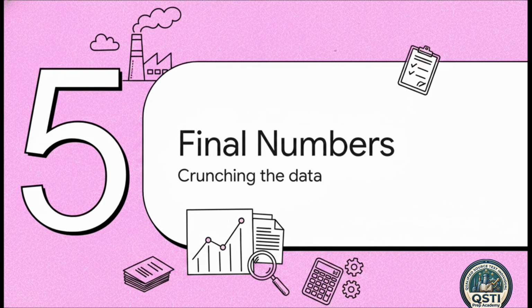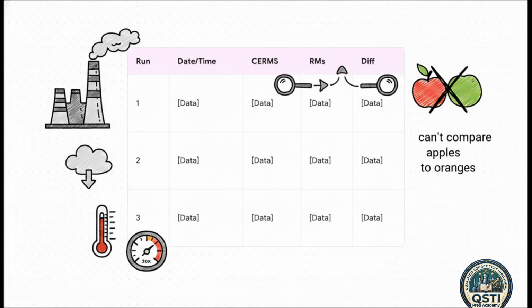Section 5, crunching the final numbers. Let's move on and see how this all builds into the actual documentation facility managers have to submit. The official documentation outlines exactly how the pass-fail data is logged in the real world. You've got your test run number, the exact date and time, and then that crucial side-by-side comparison, the emission rate determined by the CERMS right next to the rate determined by the manual reference methods. Finally, the exact difference between the two is calculated.